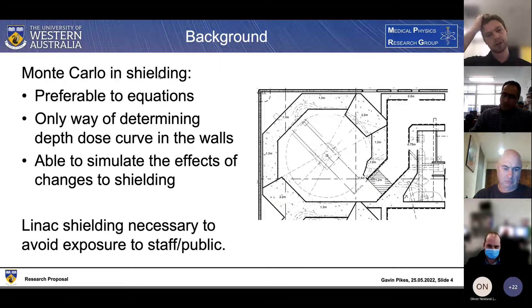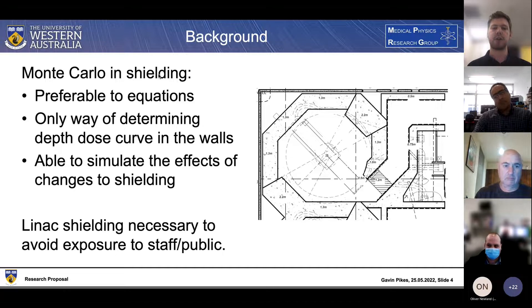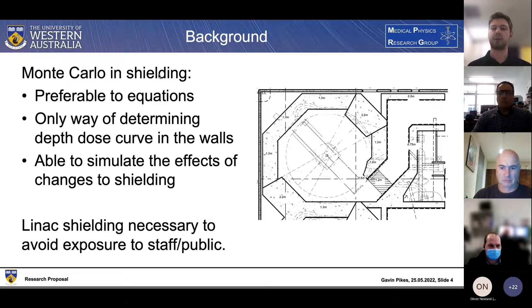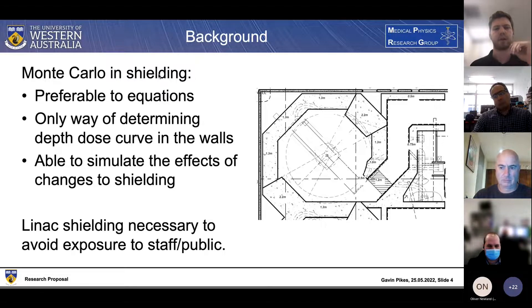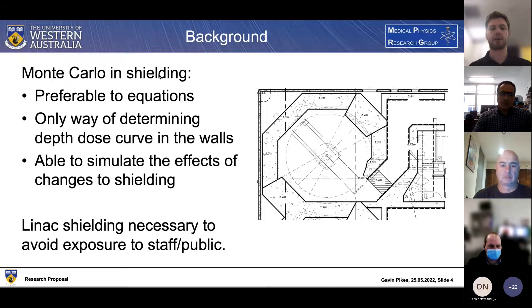Monte Carlo in radiation shielding has become a preferable method, especially compared to the equations provided by the NCRP - the National Council on Radiation Protection. The more analytical techniques are not as useful for complex bunker geometries. You can see here an image of the MARY bunker, which has quite complex geometry, meaning the simpler equations don't really provide particularly relevant shielding calculations. Monte Carlo also allows us to individualize the shielding calculations much more to our specific bunker.